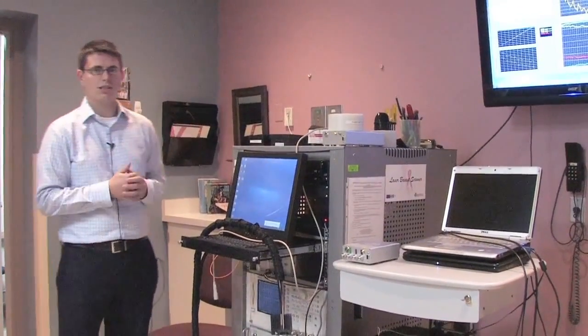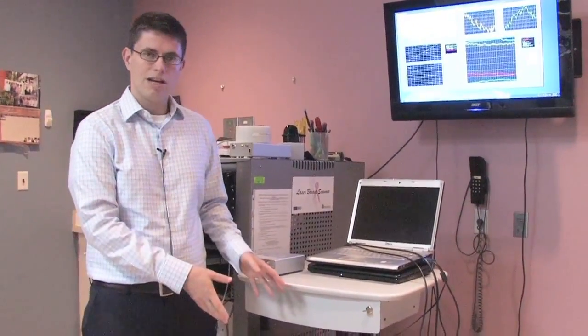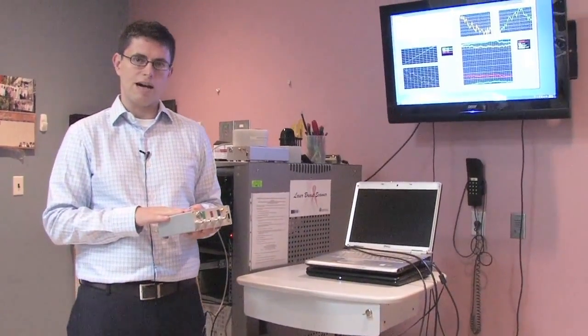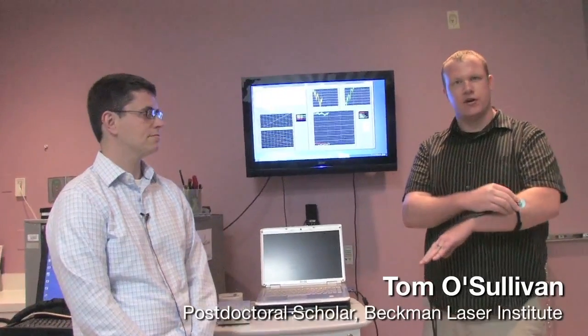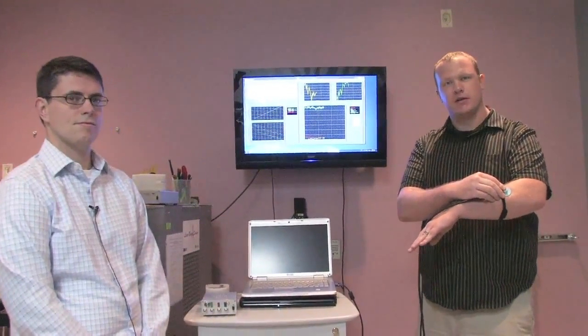This technology is based, in addition to lasers, on RF technology. This is our last generation device, and we've been able to miniaturize this instrumentation so that it's now the size of a microwave, or even the size of about an external hard drive. The capability in this box is approximately equal to the capability of this large device. I'm Tom O'Sullivan, also a postdoc here at the Beckman Laser Institute. I work for Dr. Bruce Tromberg along with Darren, and together we're going to demonstrate our real-time functional spectroscopic imaging technology, DOSI.